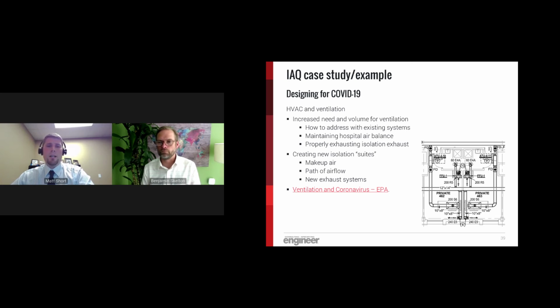So the image on the right is of a project in which we designed new systems to create an isolation space out of an existing patient room. This space was originally served from a dedicated ceiling hung fan coil unit with ducted outside air. Obviously, this is not a system that was originally intended or feasible to make up the air required for the new isolation exhaust systems or to properly treat the high volume of makeup outside air.